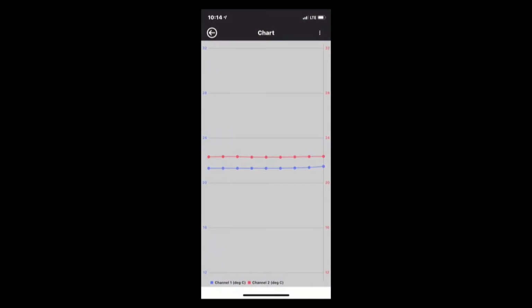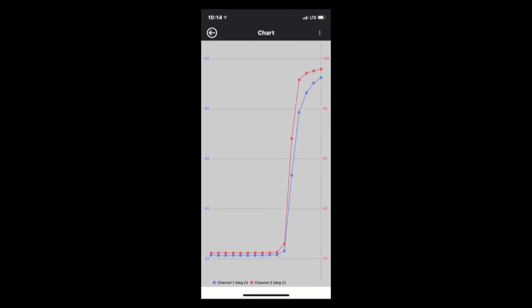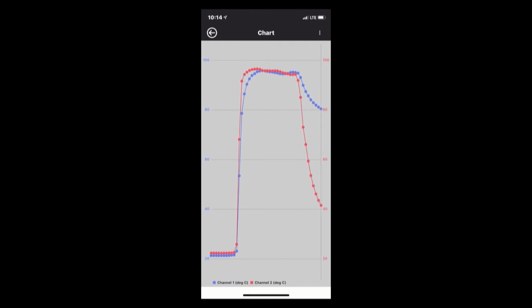So what I'm going to do is I'm going to measure the temperature of this water, and we're going to watch the response rates. It's basically sampling once a second, but you'll see just the wire probe, how much faster response is the lower mass. Okay. And now I'm going to remove them from the element. And as you can see, our wire probe, which is channel 2, is going back to room temperature much quicker than the channel 1 probe.